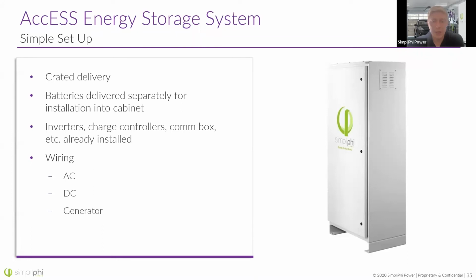Schneider currently cannot communicate intelligently with the AMPLIFI battery. However, you can still integrate it with a Phi battery. With the SimpliPhi, the standard Phi batteries, you can put as many batteries as you need in parallel, but with the AMPLIFI batteries, you can put 75 batteries in parallel. So that's well over 100, that's about 300 kilowatt hours or more. So it's not something that's going to be a limiting factor on residential systems, but maybe on a few commercial systems, you'll want to switch to Phi.